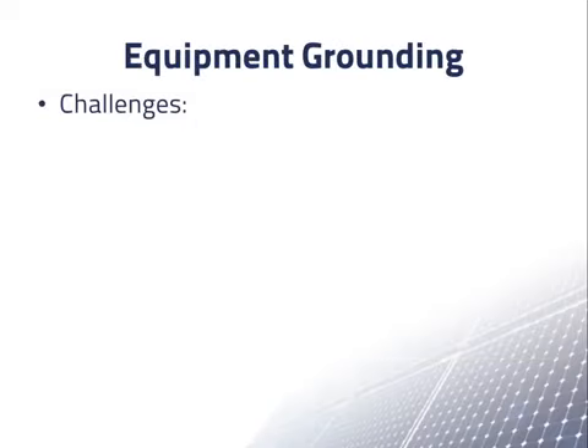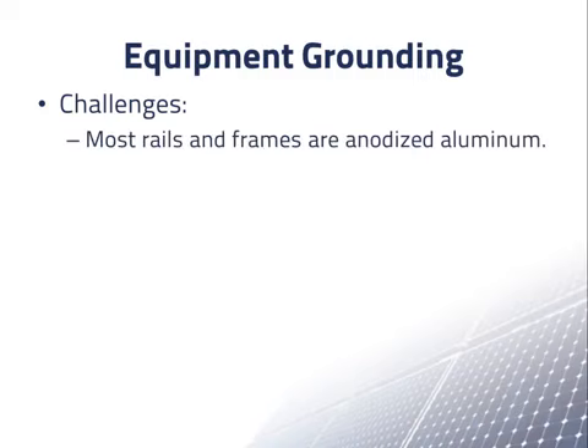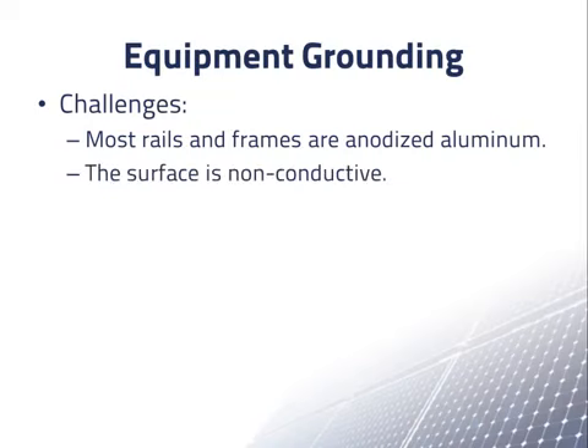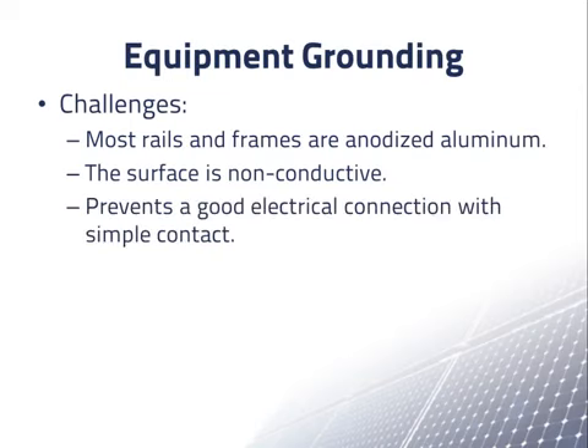There are many challenges to proper equipment grounding in a PV system. In the array, most rails and frames are anodized aluminum. This means that the metal has a relatively non-conductive layer on the surface. This surface is insulating enough to prevent a good electrical connection with a simple contact.